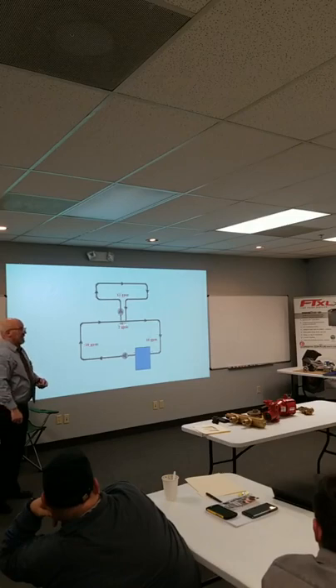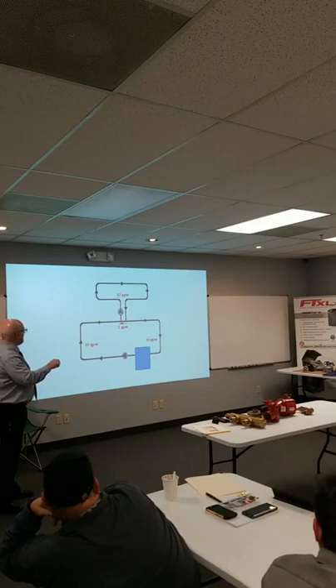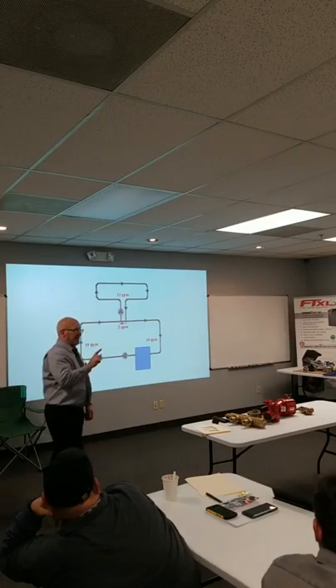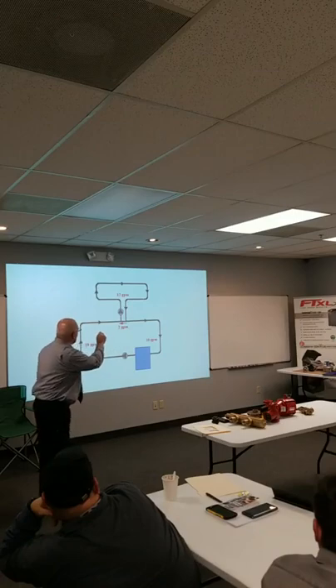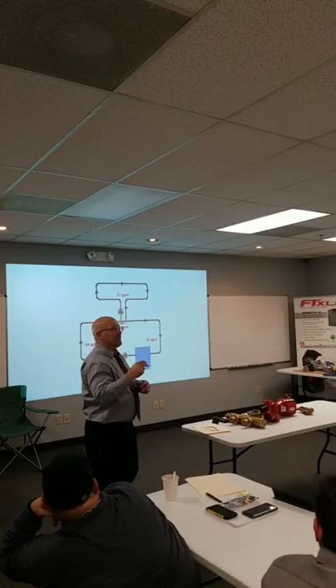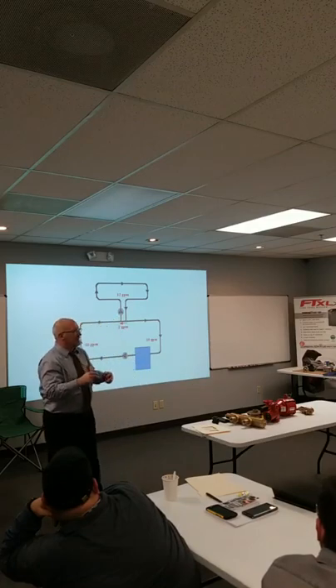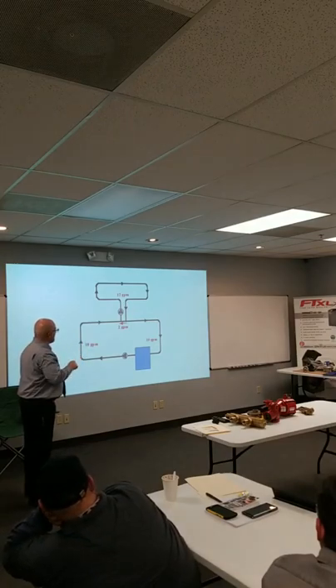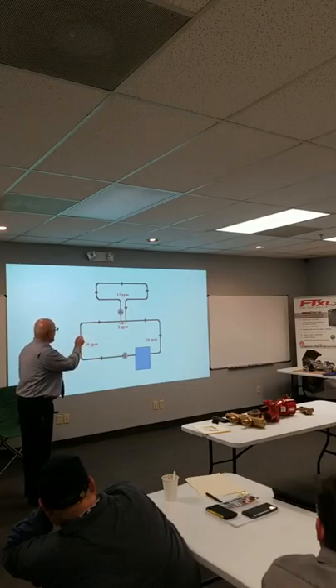Well, now I'm really going to blow your mind. Uh-oh. So now if I got 10 gallons a minute here, and I pull 12 gallons a minute out here, what do I got going through those tees? Backflow. Not negative flow. But backflow. I'm actually tempering this loop. So I can design my primary secondary system at different delta Ts and different water temperatures because of just the speed of this pump. Again, what goes into a tee must come out of a tee. If I have 10 going here, this wants 12. It's got to come from somewhere, so it pulls it back in and circulates it.